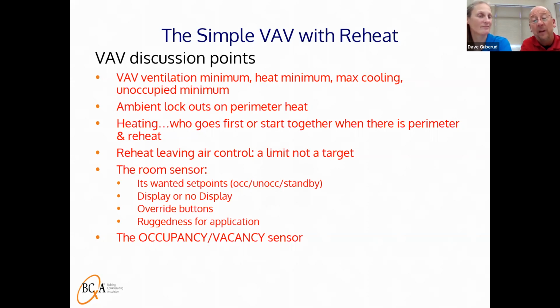simultaneously with the reheat, or a little bit ahead of it, or even opposite, which we are not proponents of. And then room sensors, again, utilizing the owner with that, right? What type of room sensor do you want? And right now, I think we're seeing more and more clients wanting to have almost like the cooler, warmer adjustment, but they don't want to display the actual temperature. Because when a person sees a number like 71, they might perceive it as cold because they keep their house at 73, right? So just not showing numbers. So again, it's a conversation that we would have, and the ruggedness to meet the application.